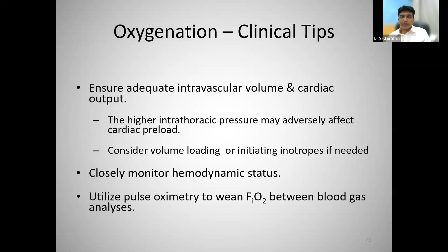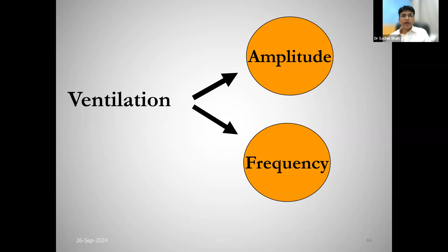Coming down to ventilation, there are 2 knobs on the machine. One is the frequency, which we usually do not touch, and one is the amplitude. Amplitude is basically the amount of wiggle that you are seeing. It is the movement of the piston, which brings about the changes in the tidal volume. So the tidal volume is controlled by the force of the oscillatory pressure that I showed you, and VTHF correlates directly to the carbon dioxide washout. VTHF is basically the tidal volume on the high frequency.